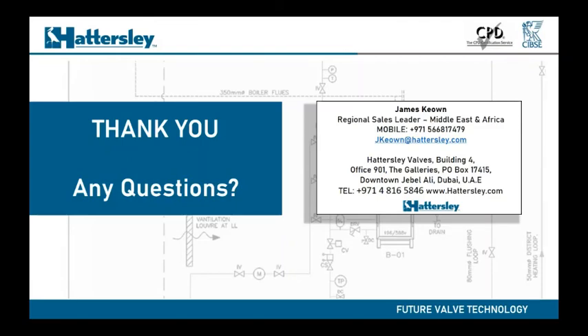Right, so moving forward, Mohammed Masihuddin asked, are PICVs leakage proof? Leak proof. No, they will always have some sort of leakage. Although they will close, they do have a leak class. I think it's between 3 and 5 or 3 and 4, depending on the type and size of the PICV. But they should never be used as isolation. They will have a slight leakage to it, but again, it's absolute minimal. But it needs to be understood that yes, it will close, but there will be a slight trickle after a while.